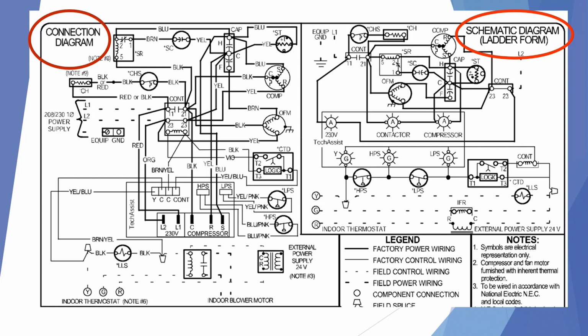This can be very important when tracking down shorts or a miswire situation in a unit to find out where each wire is located. Many times when technicians replace parts, wires may get misplaced, which causes the unit not to function. So it's very important to follow the connection diagram and make sure that every wire has been landed where it should be.